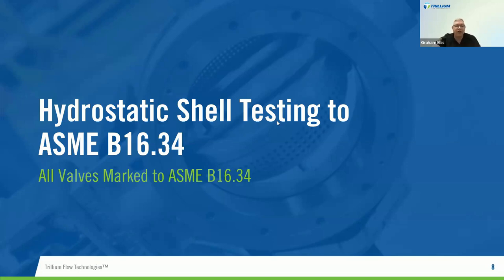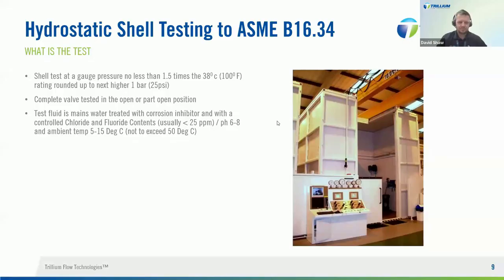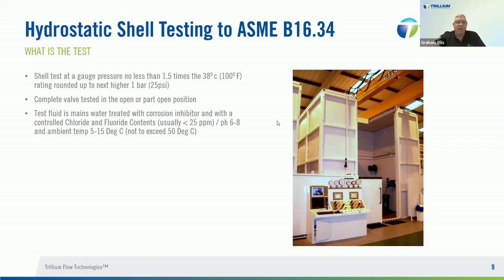This section on hydrostatic shell testing applies to all valves that we manufacture apart from valves manufactured to API 6A. The shell test is at a gauge pressure no less than one and a half times the 38-degree rated pressure, rounded up to the next higher one bar. The valve is tested in an open or partial open position. The test fluid is mains water with a corrosion inhibitor controlling chloride and fluoride content — usually less than 25 parts per million, pH 6 to 8, at an ambient temperature of 5 to 15 degrees, not exceeding 50 degrees.